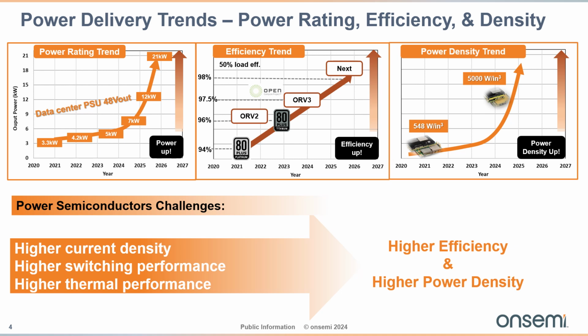Essentially, there are 3 power delivery trends: power rating, efficiency, and power density. As can be seen from the left of the slide, power rating is going up. The way to look at this is that rack size stays same along with the power supply units while increasing the power rating. This year, we are seeing deployment of 5 kilowatt designs, and in the next 3 years, we expect an exponential growth in this rating. As a result, we expect the demand for power density increases by nearly 4 to 5x during the same period.